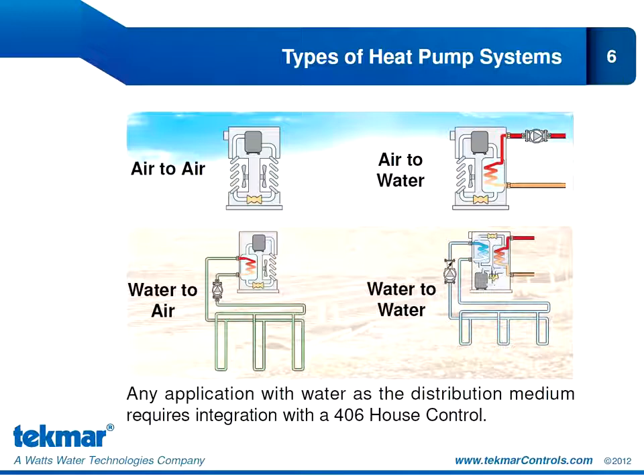Before we revisit the heat pump applications in greater detail, I do want to take a look at the 4 different types of heat pumps, because the type of heat pump you have will determine your control solution. The left-hand side of the slide shows 2 heat pumps that use air to distribute the energy to the building. We have an air-to-air heat pump, very dominant in the market, where air is being used as the energy source, and air is also being used to distribute that energy to the building. Below that, we have a water-to-air heat pump, where water is being used as the energy source, and this is typically obtained from tubing buried deep in the ground. Again, air is being used to distribute that energy to the building.